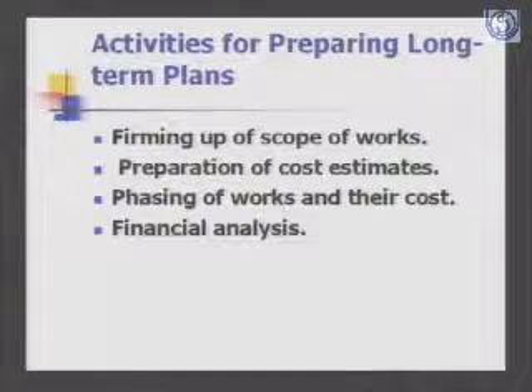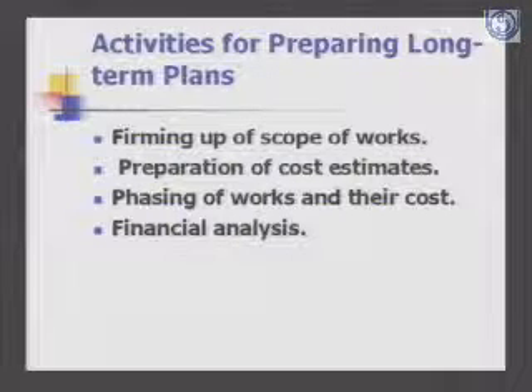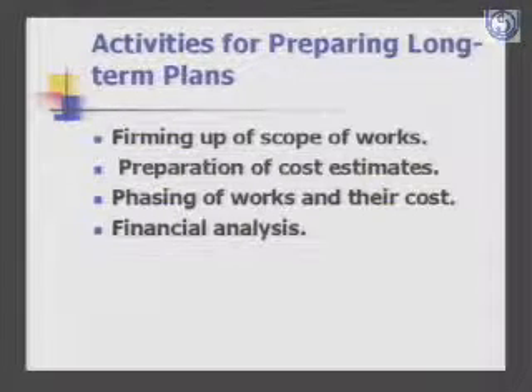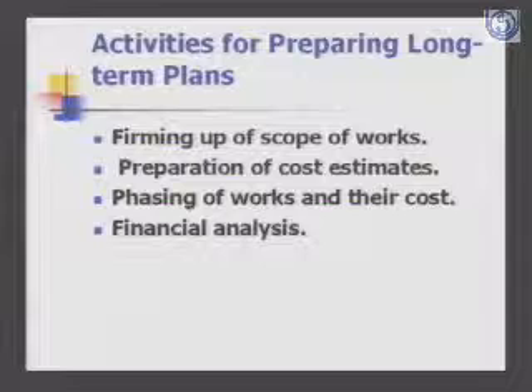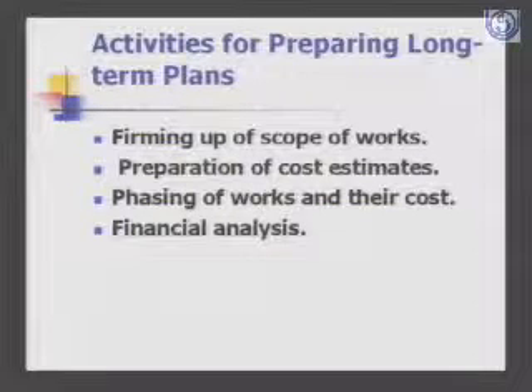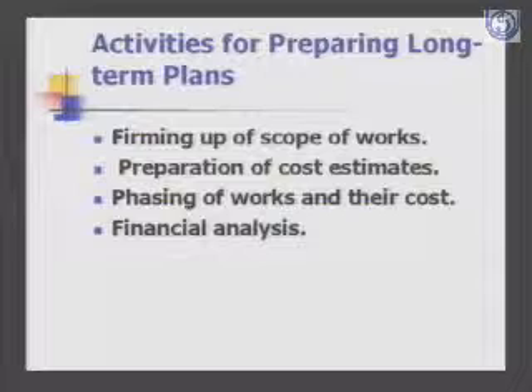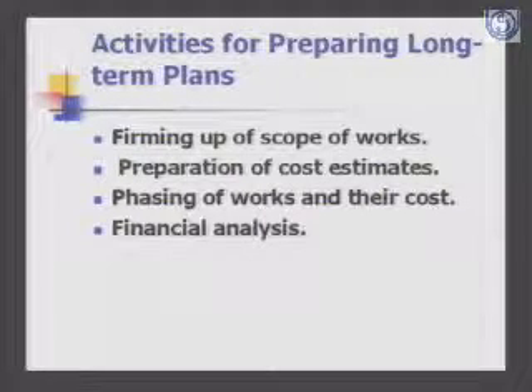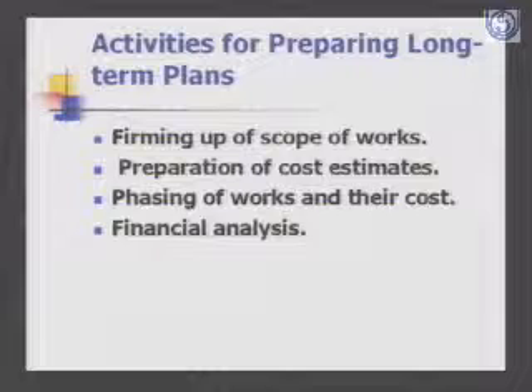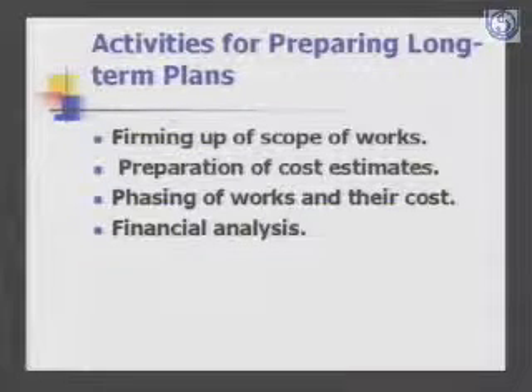Once you do that, you find an optimal solution which is least cost and has minimum losses compared to the various alternatives. You draw up a long-term plan, firm up the scope of works, prepare cost estimates, and prepare a phasing of the works, because you do not need to construct all the substations or the entire system in the first year. Load growth and improvement take place over the years, so you do works in a phased manner so that substations and lines are erected when they are required, rather than investing in advance.